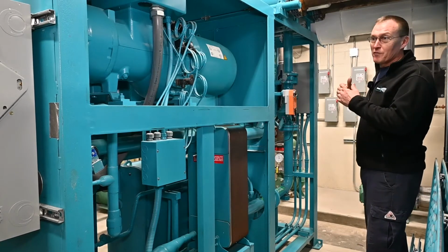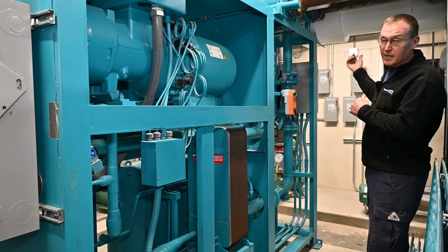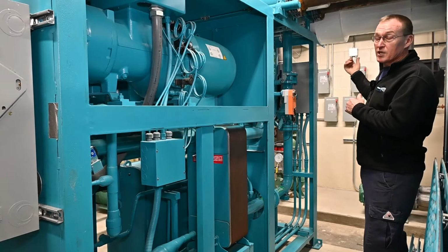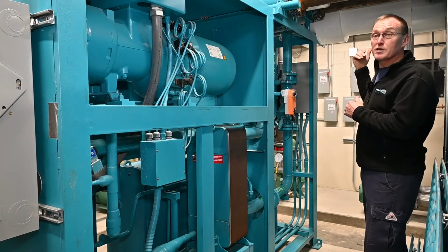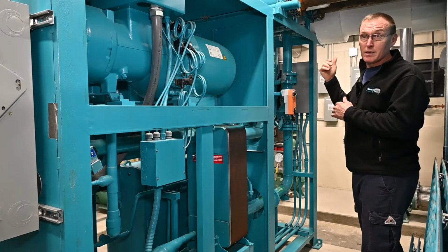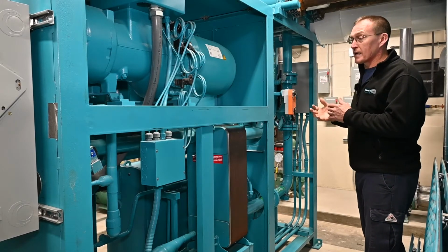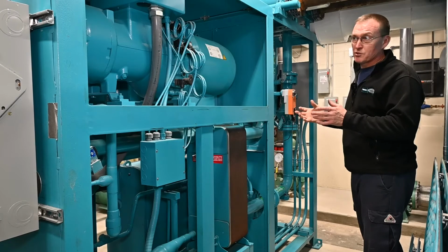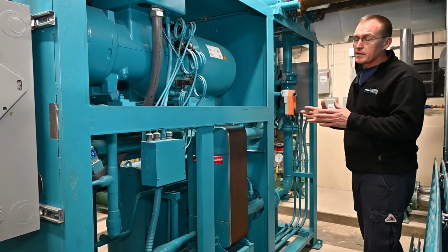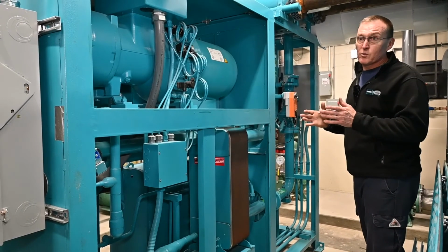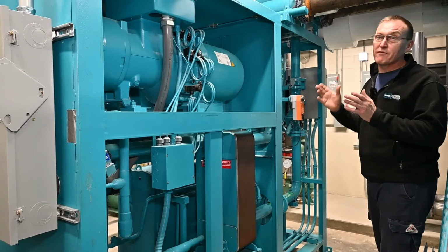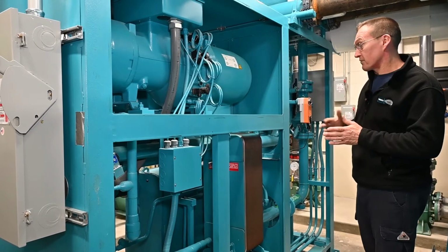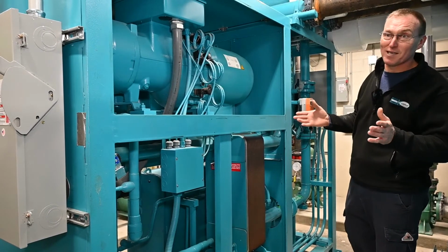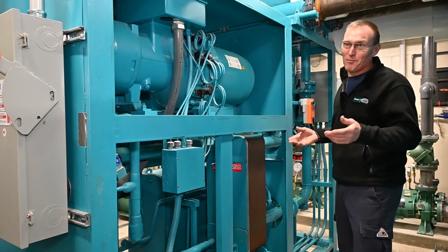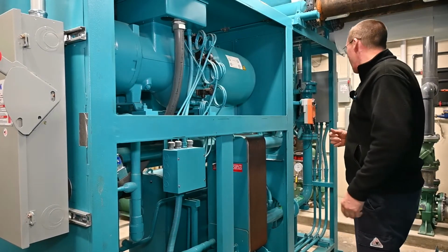And then you'll start to eventually see, depending on outside ambient conditions, you'll hear the condenser fan start to spin. Currently, based on these temperatures and run times and everything else, we don't get over about 12 hertz, so you can barely even hear that fan run. And if it's cold enough outside, you get to see it make some nice snow, because that water's that warm coming out of there.